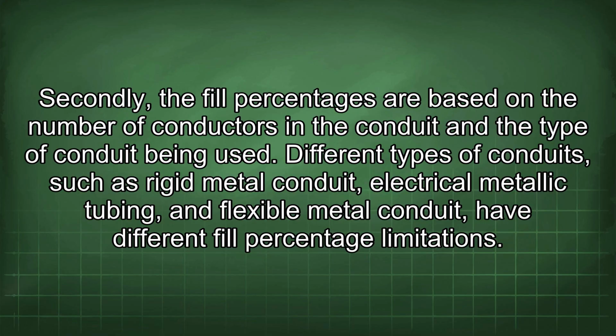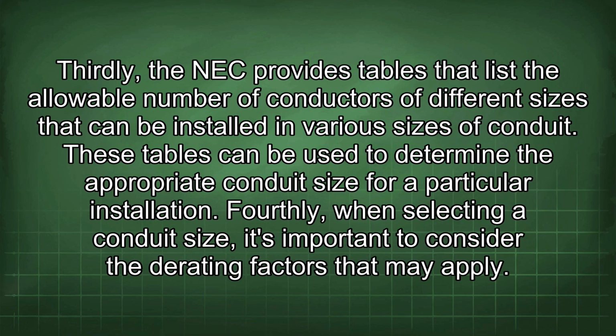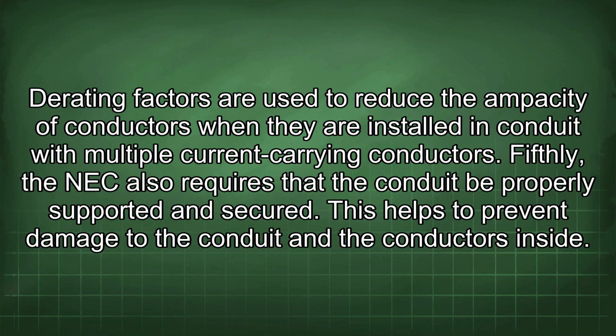Different types of conduits, such as rigid metal conduit, electrical metallic tubing, and flexible metal conduit, have different fill percentage limitations. Thirdly, the NEC provides tables that list the allowable number of conductors of different sizes that can be installed in various sizes of conduit. These tables can be used to determine the appropriate conduit size for a particular installation. Fourthly, when selecting a conduit size, it's important to consider the derating factors that may apply. Derating factors are used to reduce the ampacity of conductors when they are installed in conduit with multiple current-carrying conductors.